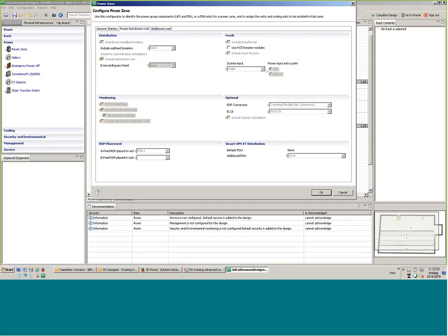I can also change to RCD breaker modules. There are countries that have RCD breakers: Spain, France, Italy, Austria, and sometimes Norway, because of break neutral. There it's pre-selected; in all other countries it's deselected. But if you want, you can push here. Just be aware, RCD uses double the amount of money, costs more, and also uses double the amount of space.